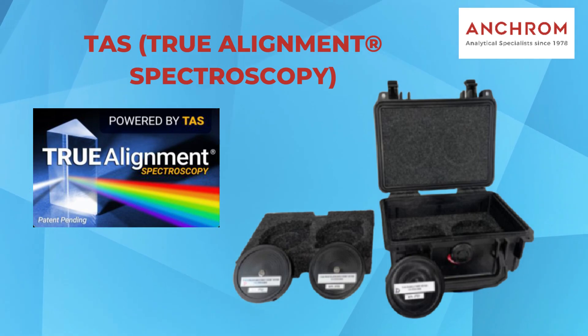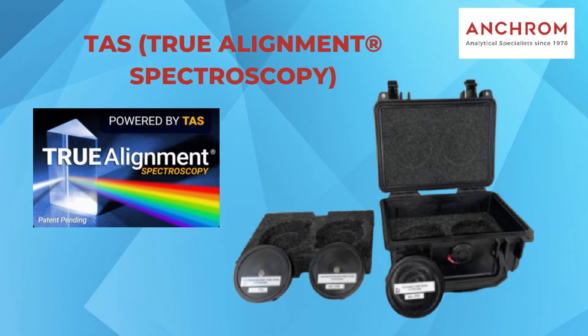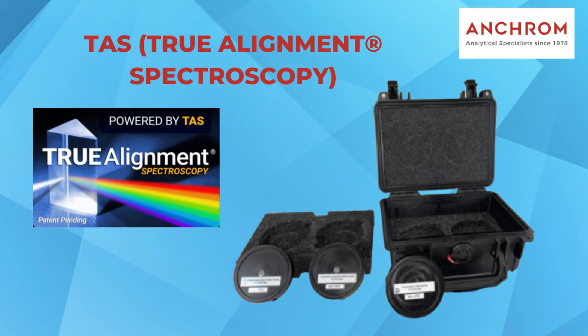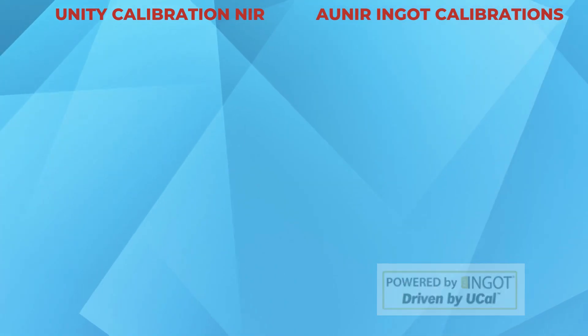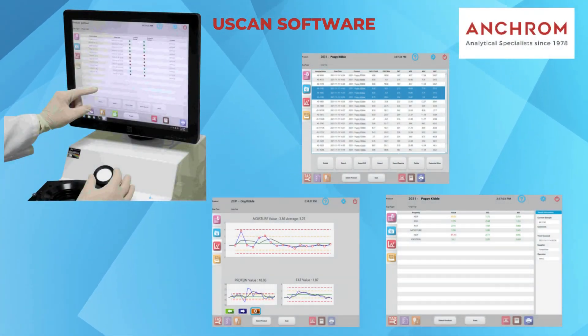This method, backed by calibrated NIST traceable standards, detects and corrects any changes caused by shock, temperature variations, or lamp fluctuations. The NIR SpectraStar comes with calibrations from Unity, and it also offers industry-leading calibrations from Aunir. These calibrations cover a wide variety of sample types and constituents, ensuring accurate and reliable results.